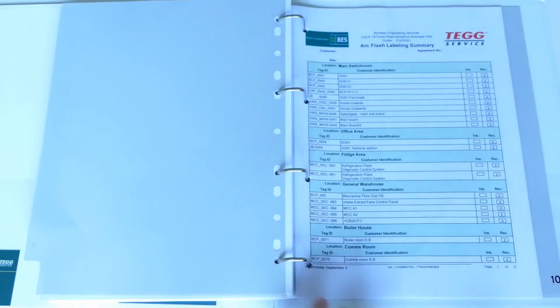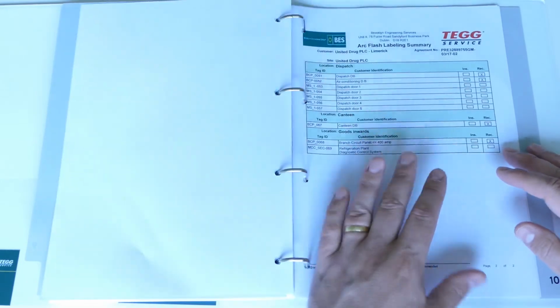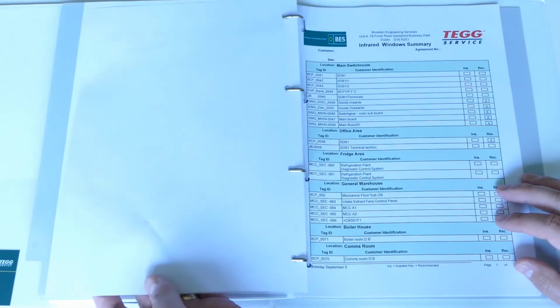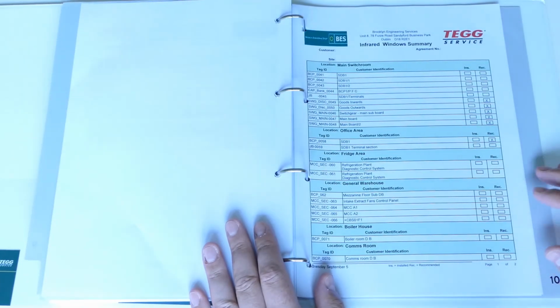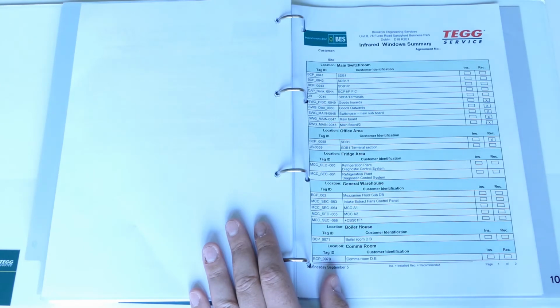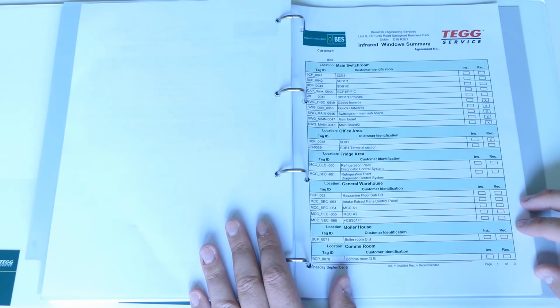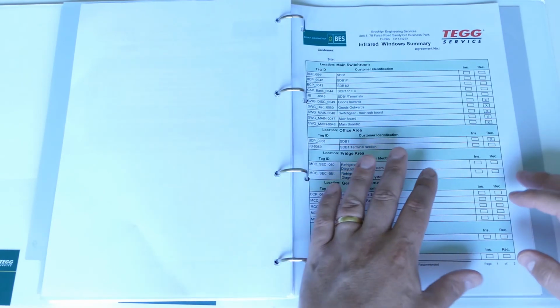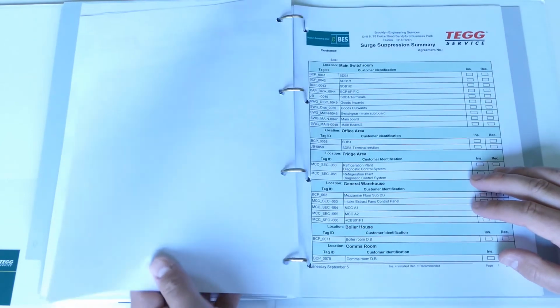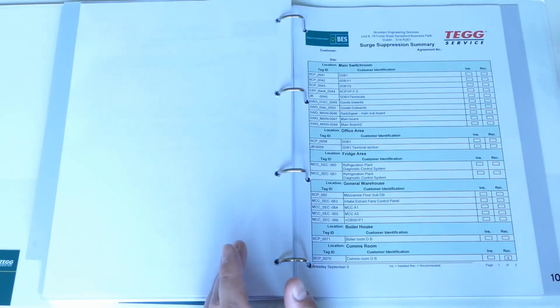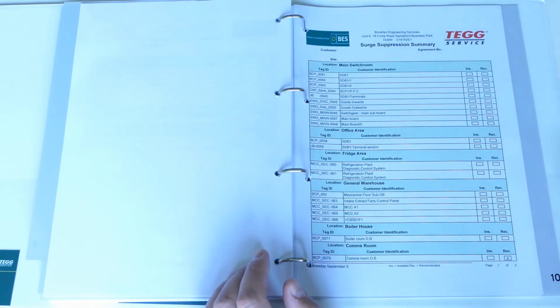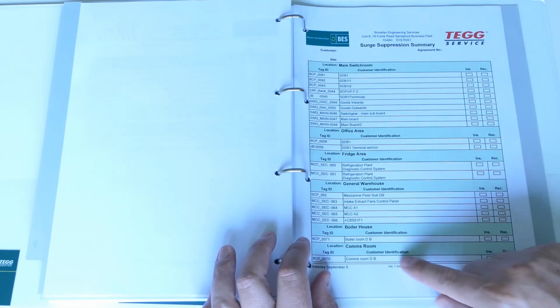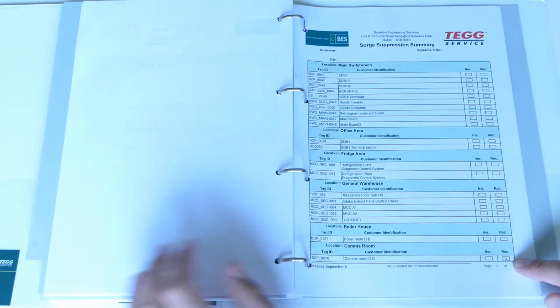We then do also make some recommendations such as arc flash labelling, infrared windows. For example, if older switchgear cannot be overridden while it's energised, we can retrofit infrared windows into the switchgear, so we can then carry out an infrared test through the window without opening the switchgear. And then finally, if our technicians spot any critical equipment that does not have surge suppression fitted, we will indicate that and also recommend that the surge suppression is fitted.